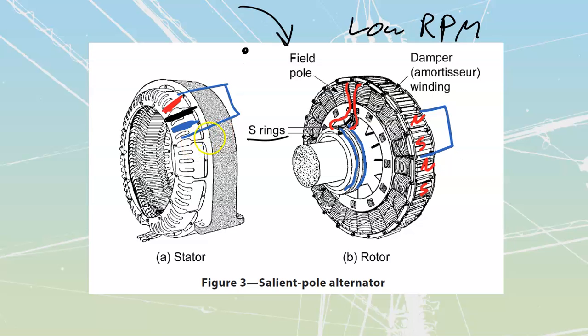So I'm going to take my main power off the stator over here at the bottom. You can see the main leads coming off of that thing. I know they're not in sequence right now, but that's all right. We pull those off the bottom, and we can carry massive amounts of current and voltage out of these because there are no brushes, commutator, arcing, or sparking. We rotate it inside of here, and it's going to be relatively slow.